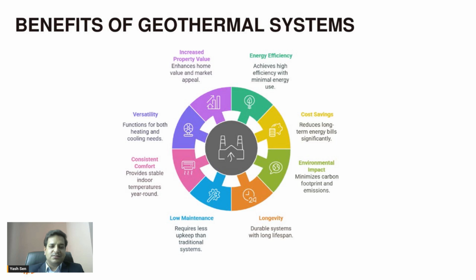Longevity - these loops work for 50 plus years and the ground source heat pumps work for 25 plus years. VRF systems normally work for 12 to 15 years, and chillers have a life of 15 to 18 years. But geothermal systems work for 50 plus years, so we have huge potential in the opex calculations when considering maintenance and system life.